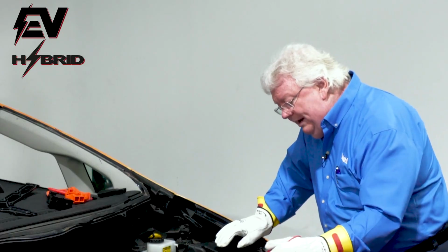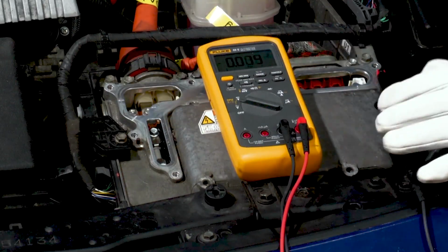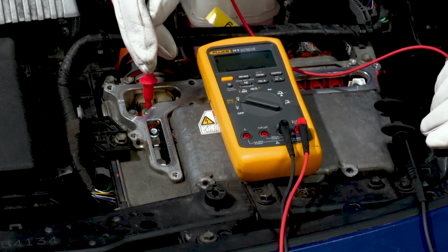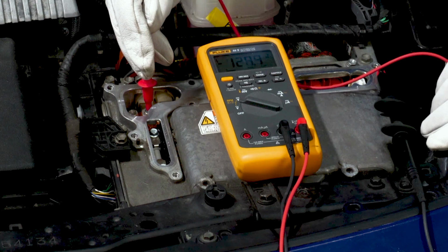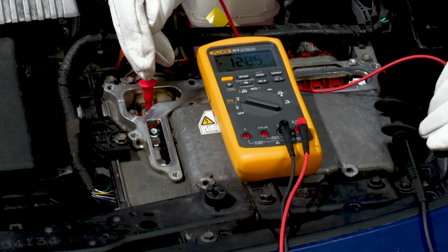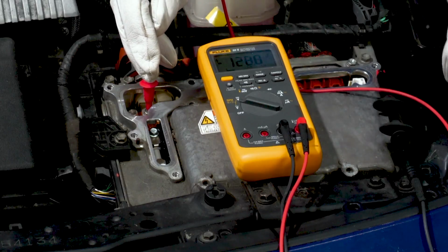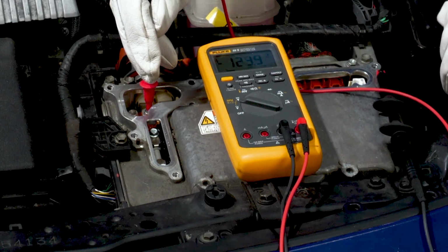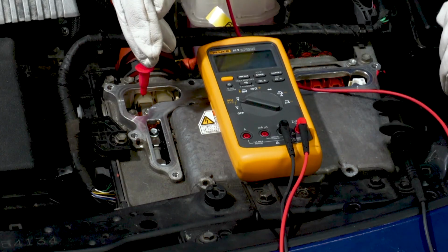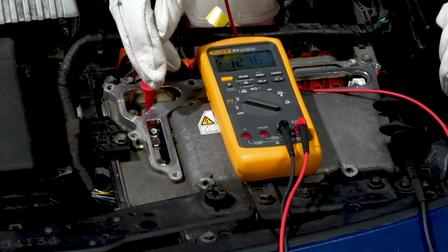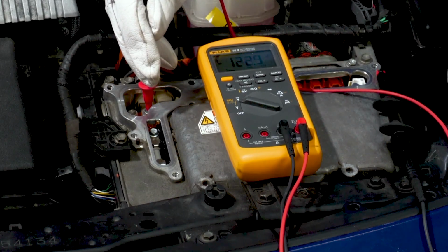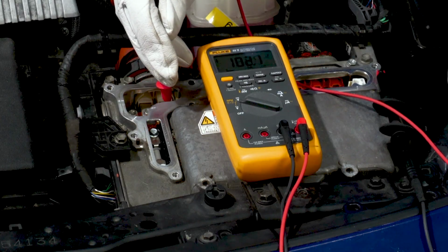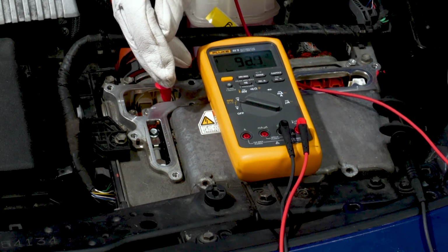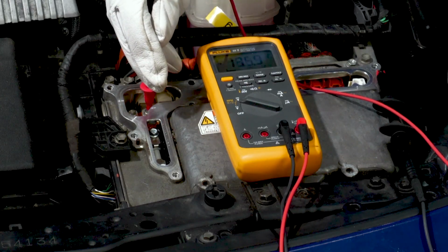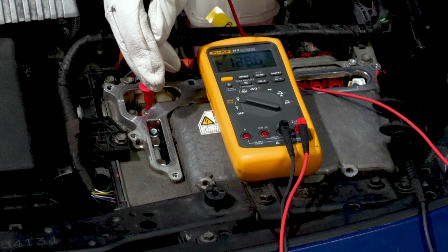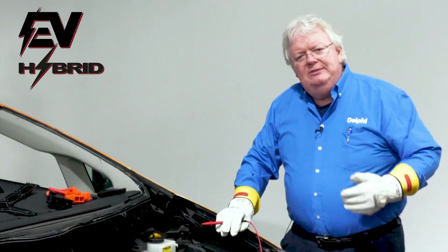I've got it set for DC auto ranging. I'm going back to the positive 10 millimeter screw that holds the positive orange cable, and I'm seeing voltage. Now I shouldn't see voltage between chassis ground and the positive, and I'm at 12.5 volts and fluctuating. I've noticed they all do that. I go over to the negative high voltage, and I see a negative sign, also around 12.3, fluctuating back and forth between the two. Oh wait, this one is actually a little lower, 9.2, 9.5, fluctuating. 13.0, fluctuating. What we're having here is an anomaly. This is normal, this is what I've seen.